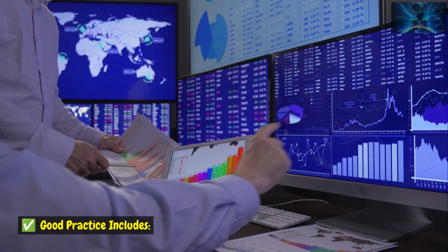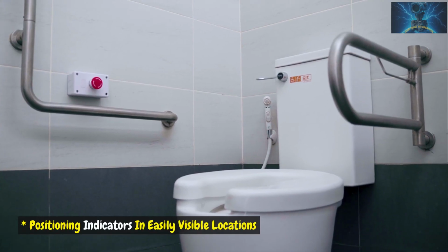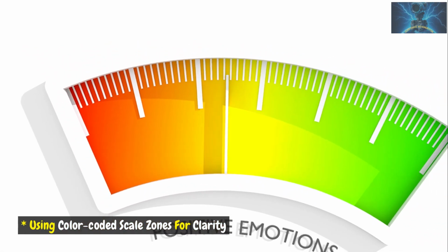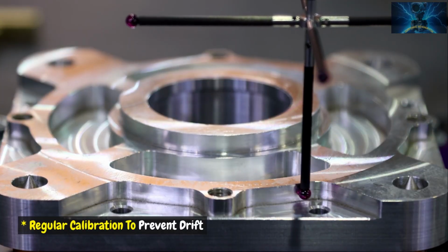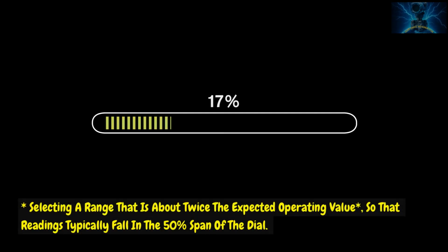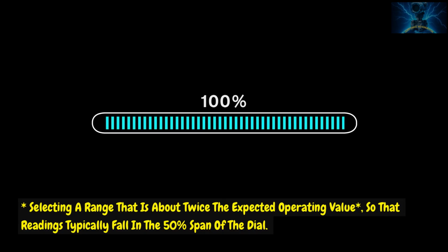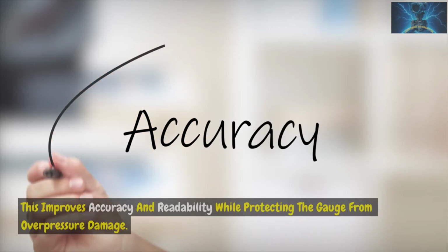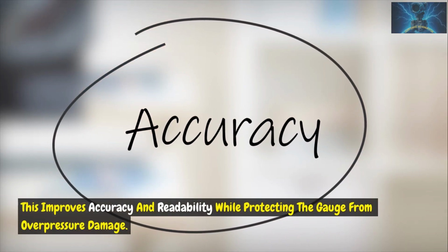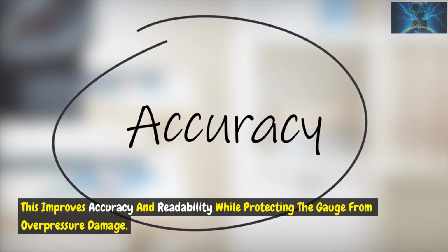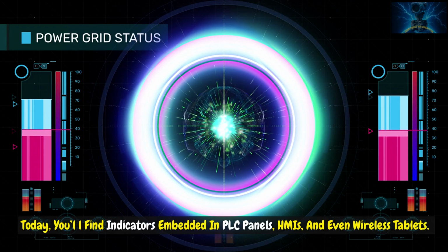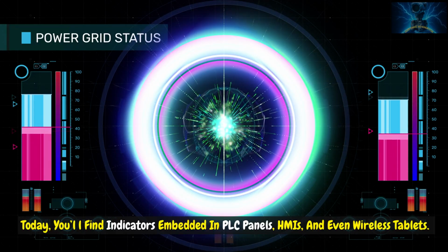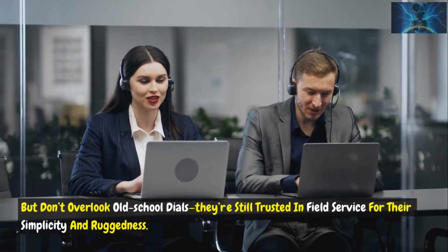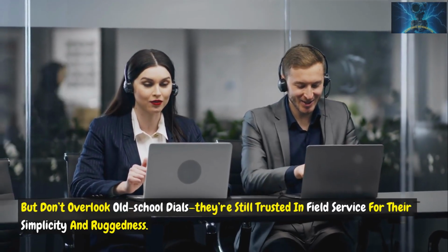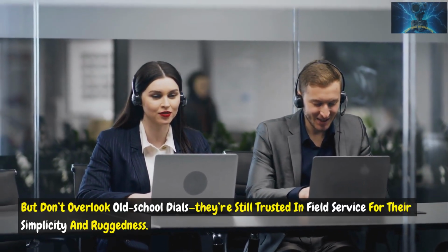Good practice includes positioning indicators in easily visible locations, using color-coded scale zones for clarity, regular calibration to prevent drift, selecting a range that is about twice the expected operating value, so that readings typically fall in the 50% span of the dial. This improves accuracy and readability while protecting the gauge from overpressure damage. Today, you'll find indicators embedded in PLC panels, HMIs, and even wireless tablets. But don't overlook old-school dials. They're still trusted in field service for their simplicity and ruggedness.